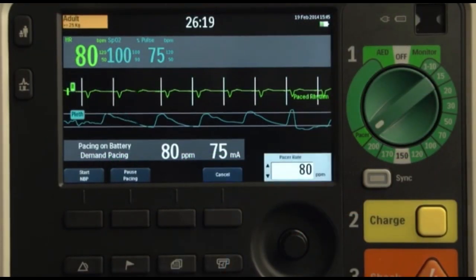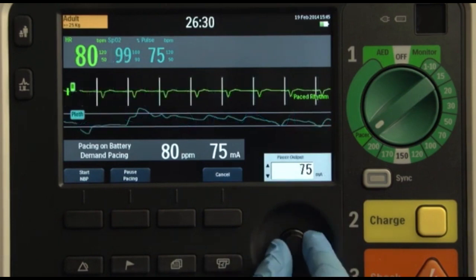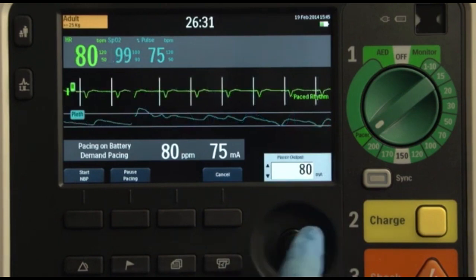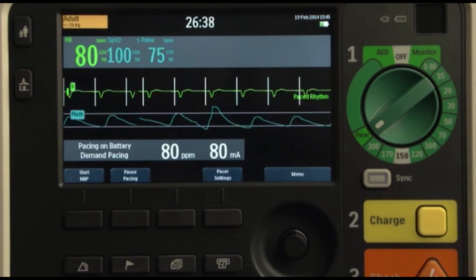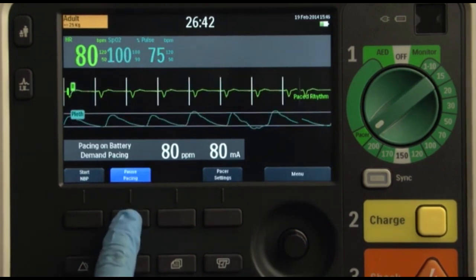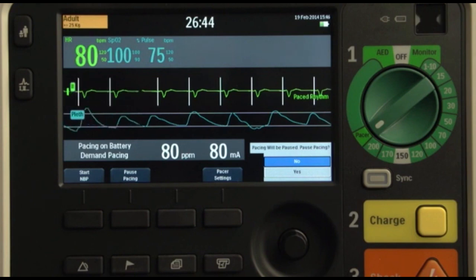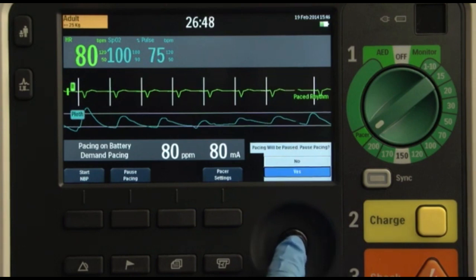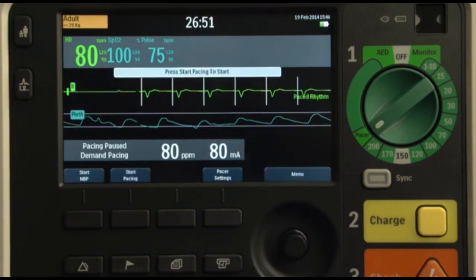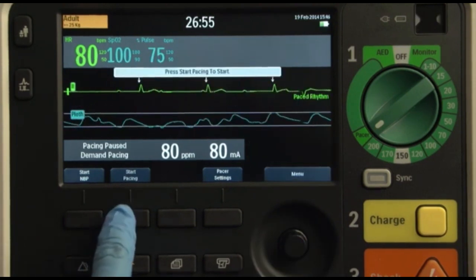The advantages of demand mode pacing are: competition between the pacemaker's stimuli and the intrinsic heart rate is minimized, decreasing the risk of R on T; and the number of pace pulses introduced are minimized, reducing patient discomfort. For this reason, demand mode pacing is primarily used as the default setting.